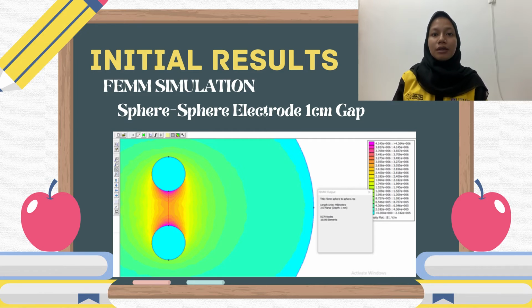Here is the result for the 1 cm gap. The density is greater at the curve of the bottom electrode, which is connected as ground. This describes the highest field intensity spot, Emax, which is the highest probability location where breakdown may occur.